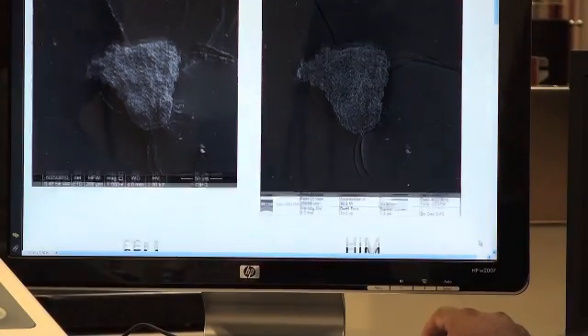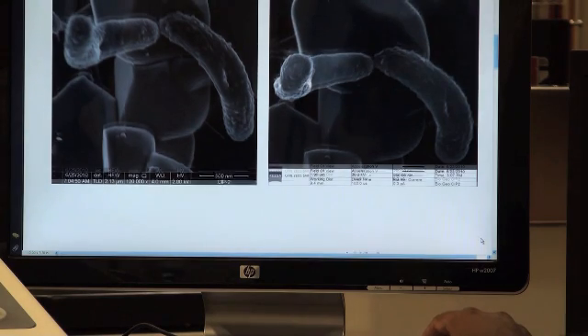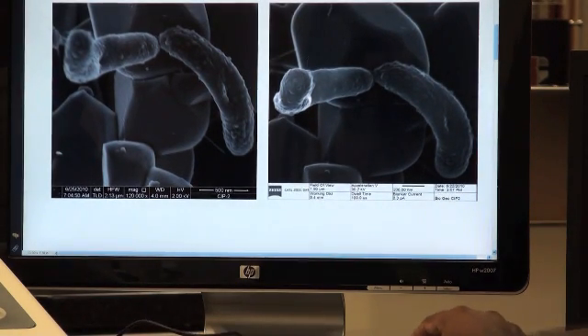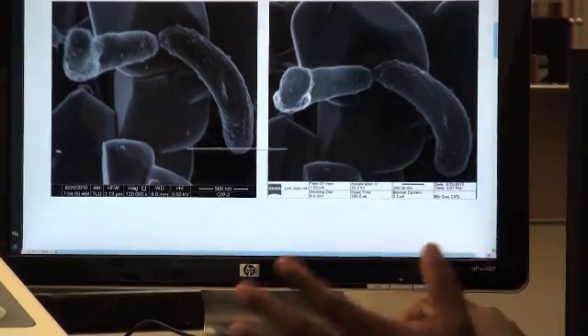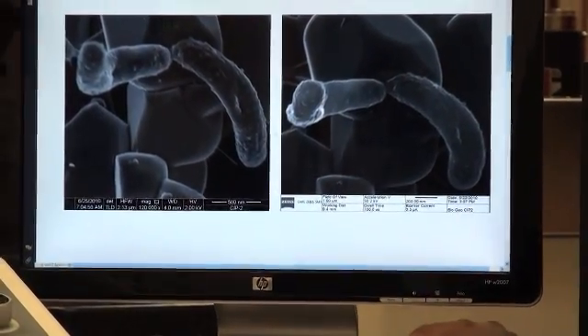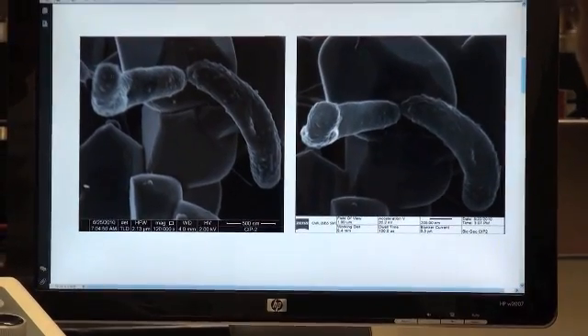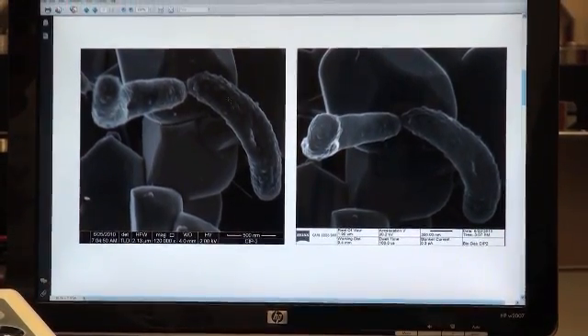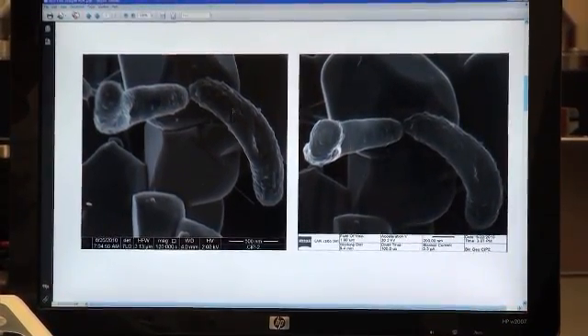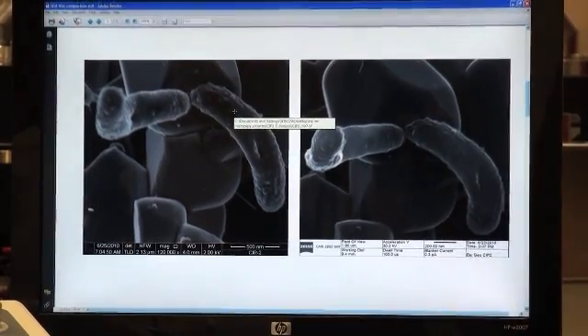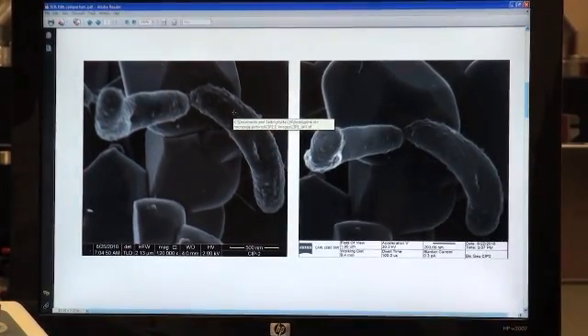So now we go to a little higher magnification. So this is again a SEM image and this is a Helium Microscope image. Again if you look at it like this, you don't see much difference. But if you zoom in nicely, you can see this one is out of focus, this one is focused, right? So that is the main problem with the SEM, the depth of field is very limited.